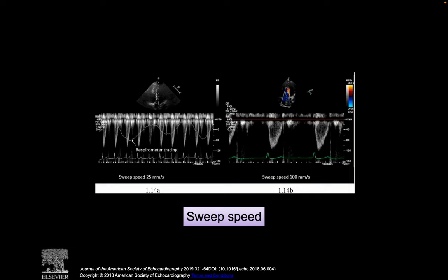Sweep speed is quite an important feature, especially in the focus world, where you'd like to compare what's happening in various phases of the respiratory cycle, so inspiratory flows versus expiratory flows throughout various valves. So that is your sweep speed setting. When you set your sweep speed high, 100 millimeters per second, your LVOT VTI will be big. So when you want to measure it, when you want to trace it, you set your sweep speed rather high.